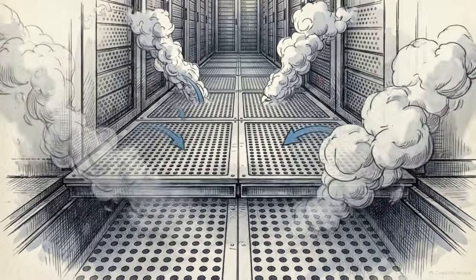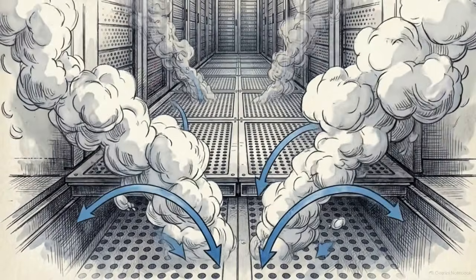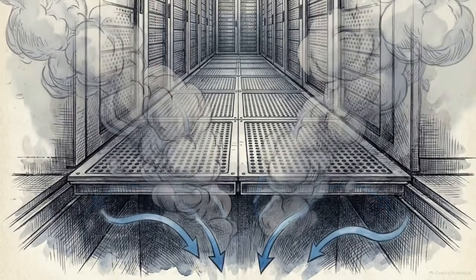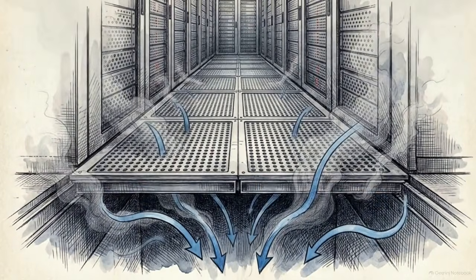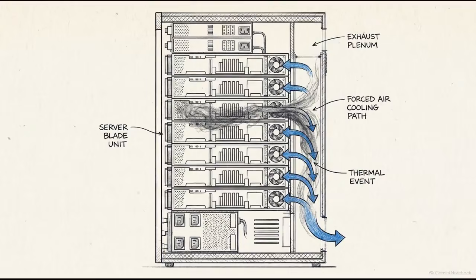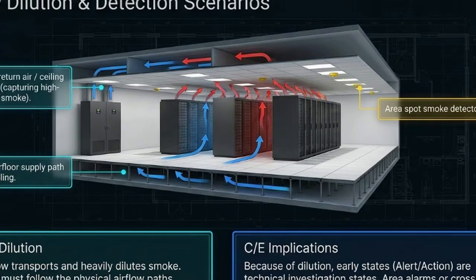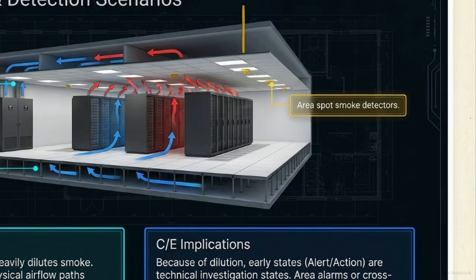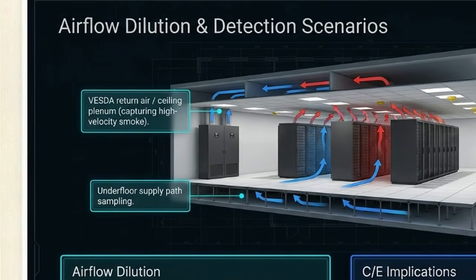Data halls utilize massive volumes of forced air to keep servers cool. These high-velocity air currents drastically alter normal smoke behavior, preventing a thermal plume from rising neatly to the ceiling. This cross-section shows the physics of airflow dilution. High-velocity supply air, marked in blue, transports and heavily dilutes the smoke. Because the smoke is so scattered, traditional area spot detectors are entirely inadequate for early warning. Instead, detection must map perfectly to the physical airflow paths of the specific room.